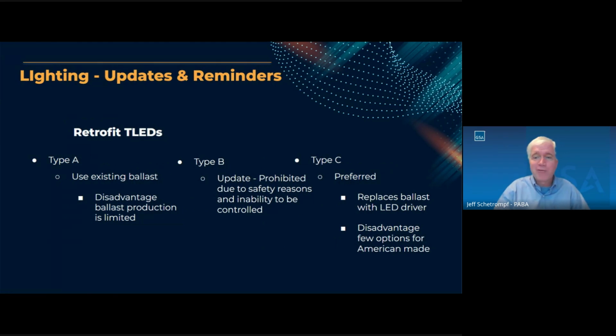All right, well, we're talking about retrofits. There are three basic types of retrofits, types A, B, and C. Type A is where you're basically replacing the bulb. The existing fixture remains intact. You reuse the ballast. This is the cheapest method for installation. It's going to generally save you energy. The drawbacks are that it doesn't save as much energy as the other methods, and you're reusing the ballast, which is going to become more difficult to replace in the out years.